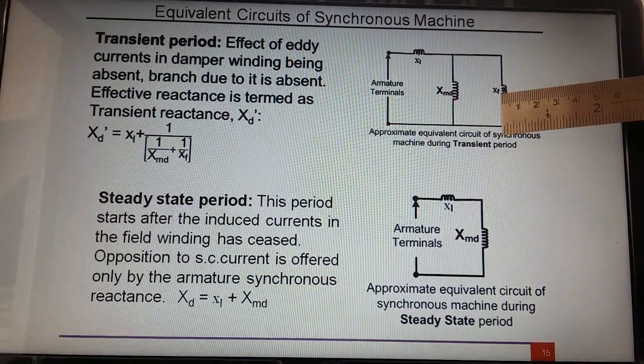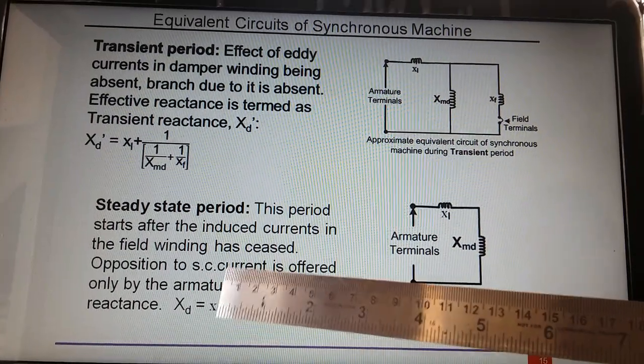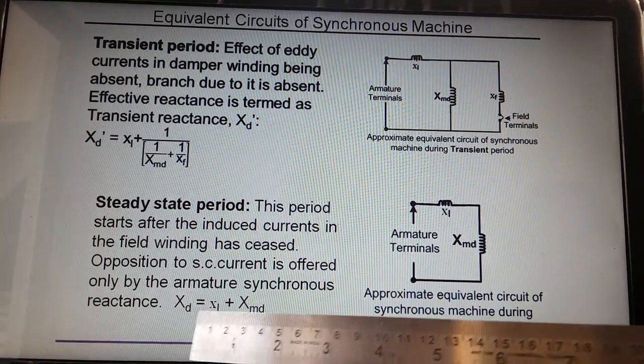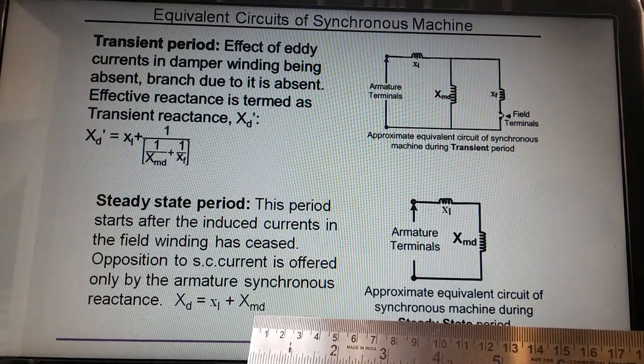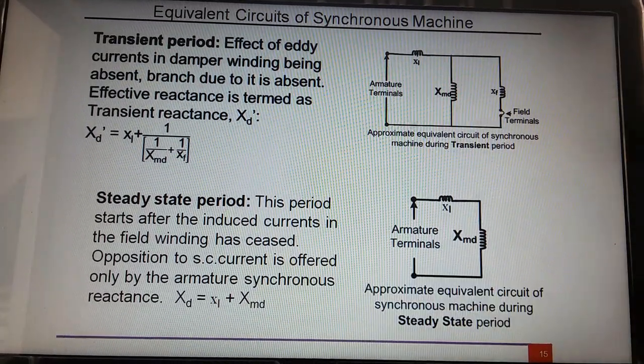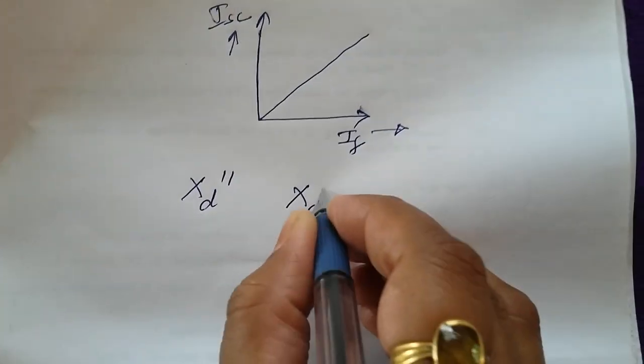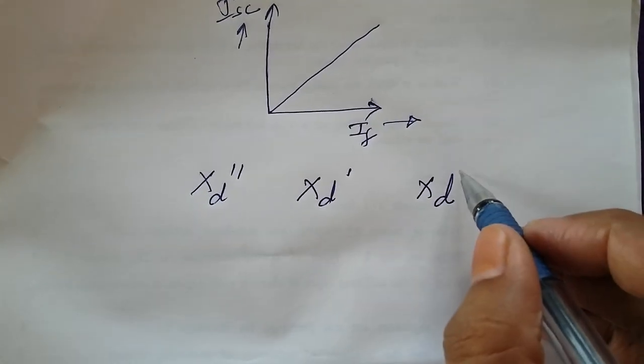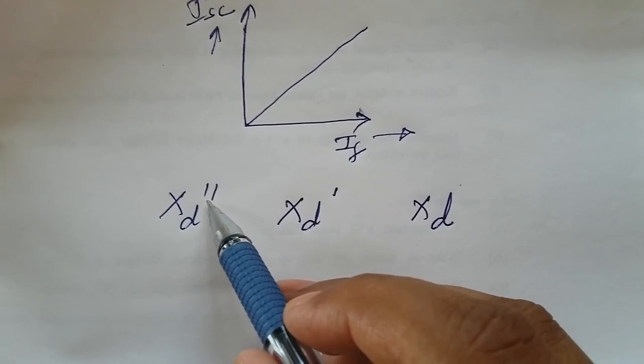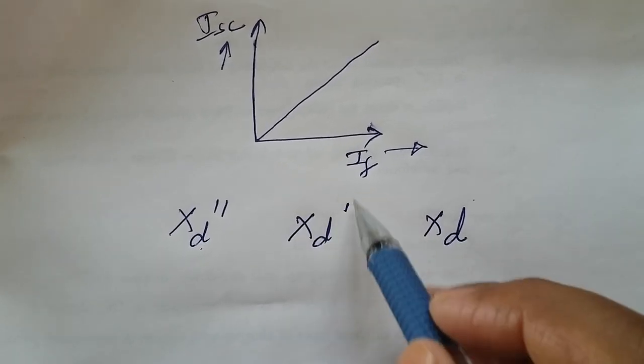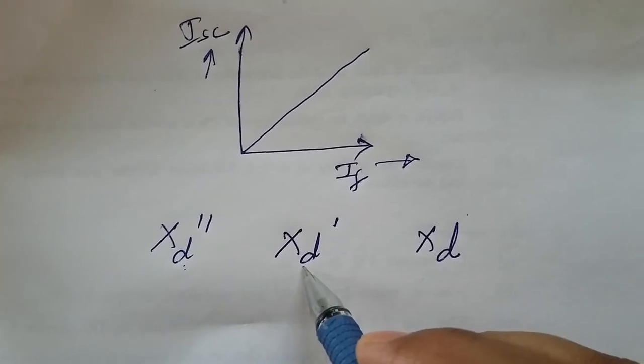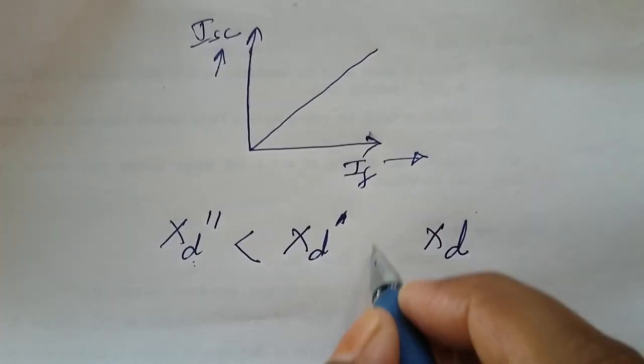The last state is the steady state period, where the time constant of the field winding is small so it also dies out. In that equivalent circuit, there is no field winding — only armature reactance is present. The opposition offered to short circuit current is only the armature synchronous reactance XD, that is XL plus XMD, where XMD is also termed XAD. Looking at all three reactances, XD is greater than XD' because XD'' has three reactances in parallel making the net reactance less. So XD'' < XD' < XD.